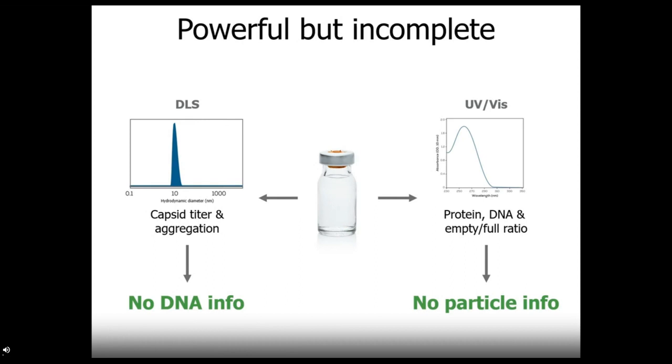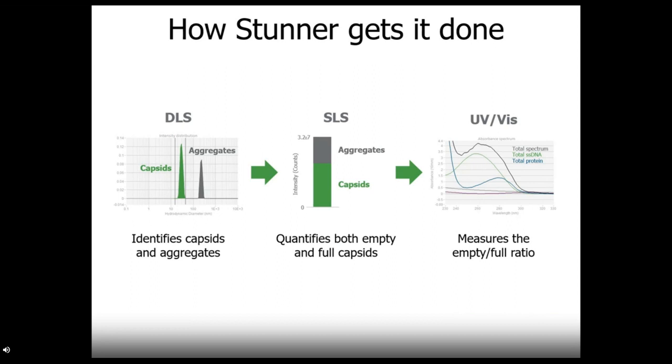So let's focus in on two technologies, DLS and UV-Vis. Each of them tells a part of the story. DLS gets you info on capsid titer and aggregation, but can't say anything about what's happening with DNA. On the other hand, UV-Vis gets you total amounts of protein, DNA, and can link those to empty full ratios. But it doesn't give you info about if any of this is actually contained in capsids. So each technique gets you valuable info, but neither tells you everything. So what if you could combine them to get a whole story? And that is exactly what Stunner does. And it's shown step by step here. First, DLS identifies the capsids, the aggregates, and how intense the signal is from each of those populations. In the middle, that info then helps you split up your SLS signal from a total into the amount just attributable to empty and full capsids combined. And finally, UV-Vis brings in that info about empty full ratio plus protein and DNA totals to provide the last piece of the puzzle.